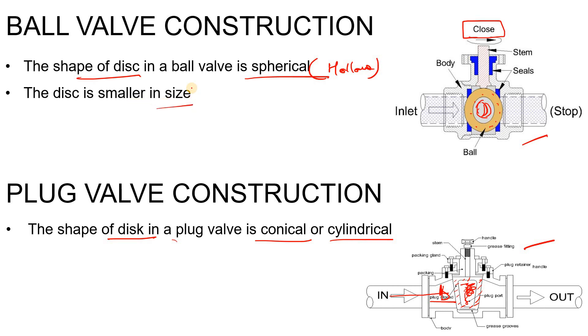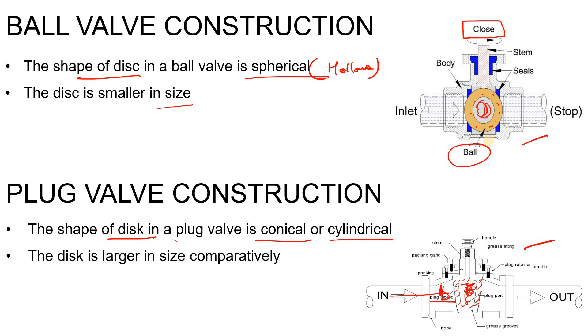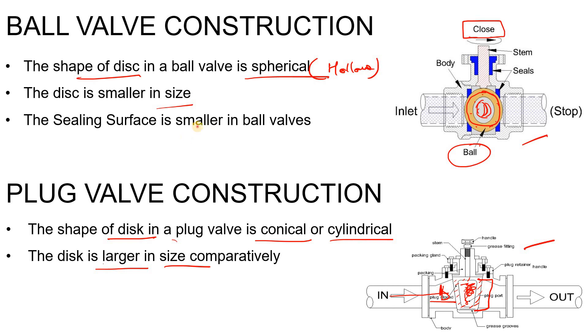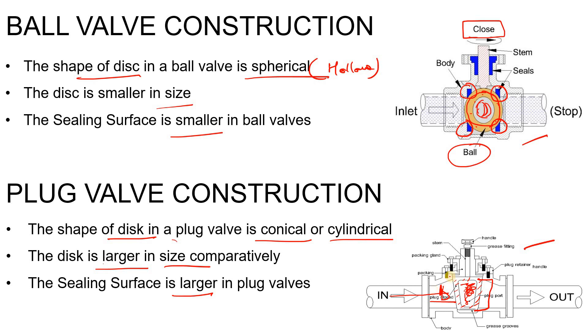In the ball valve, the disc is smaller — it depends on the size and where you are installing the valve, but most of the time the disc is in the shape of the ball. In the case of the plug valve, the disc is relatively larger in size compared to the ball valve. The sealing surface in the ball valve is smaller, as you can see here — this blue area is your sealing surface. In the plug valve it is larger, because if the sealing is not better there could be leakage.